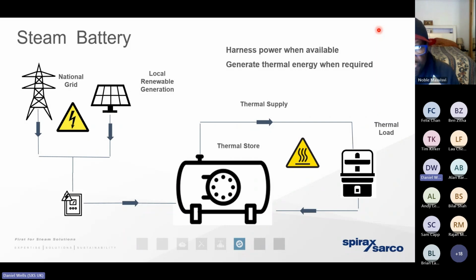This is what we call a steam battery. So if you can imagine a vessel of hot water, or a vessel of water, we've got electrical elements running through that vessel. These are generally low voltage elements. So we can use grid electricity, we can use renewable electricity to heat up that vessel of hot water. Remember, there's a pressure temperature relationship. So if we elevate and pressurize to approximately 30 bar gauge, that's around 225 degrees. That water sits there, a single phase, high temperature, high pressure, until we need the steam. And when we need the steam, we can achieve it just by depressurizing that vessel. So this ties in very, very closely to the principles that we've gone through previously in the steam tables.